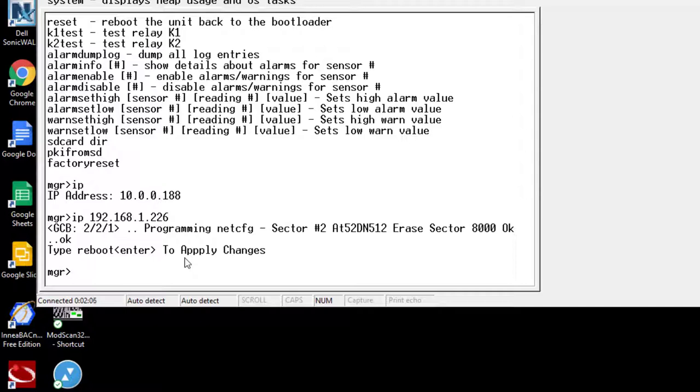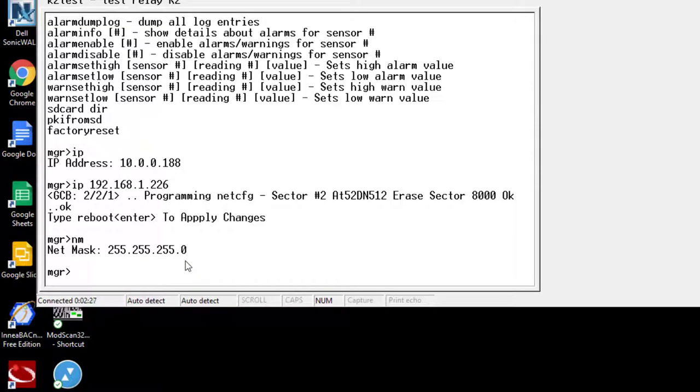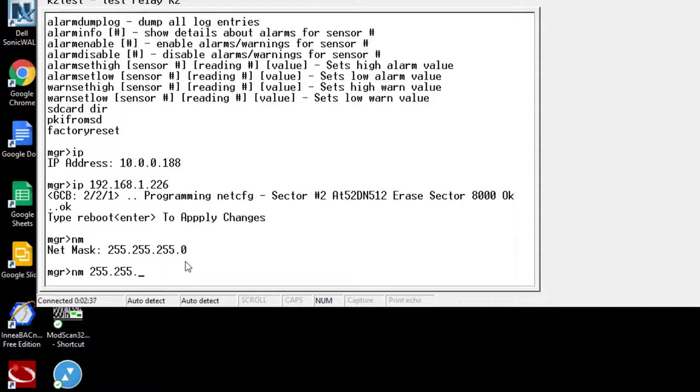Next based on IP communication, we need to make sure that net mask is set correctly. So if I type in NM for net mask, enter, we see it's 255.255.255.0, which is perfect for what my 192.168 is going to be communicating as. If I wanted to change it to something different, I would just type in NM space and then whatever that may be. But in this case, we're not needing to change it.